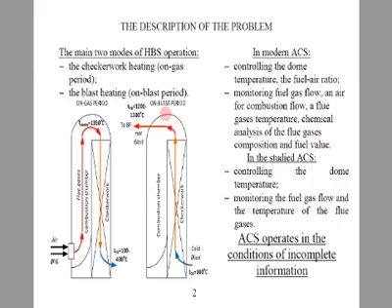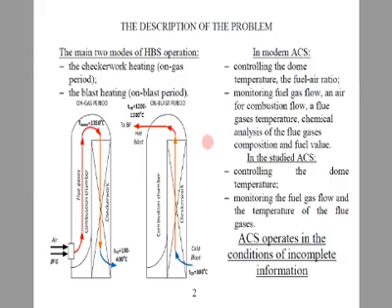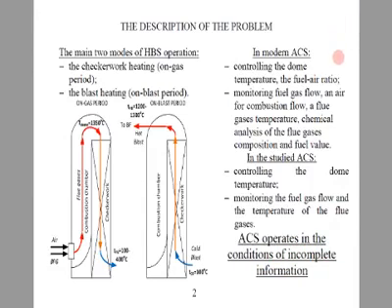In the on-blast period, blast furnace air passes through the hot checkerwork in the direction opposite to the combustion products, taking heat from the checkerwork. In the case of operation of HBSB which includes 4 units in sequential mode, 3 HBS operate in the on-gas period and 1 operates in the on-blast period. In the studied system, there is a system for controlling the temperature and a system for monitoring the fuel gas flow and the temperature of flue gases. Such a number of parameters does not allow a clear understanding of process quality.